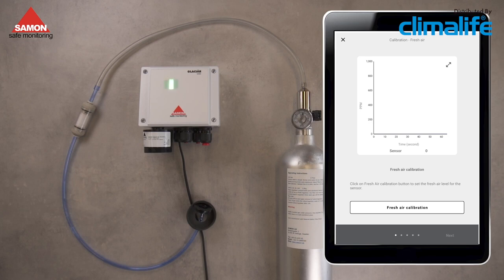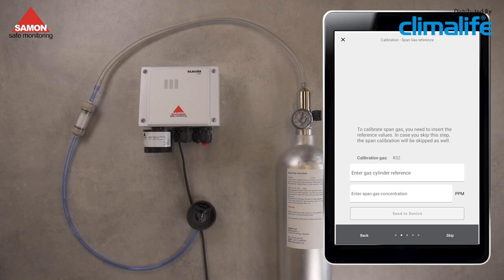Before connecting the calibration kit, make sure the sensor is ready and free of gas or other sources of pollution. If a clean environment can't be made, use natural fresh air for zero calibration. Click Fresh Air Calibration at the bottom, then select Next. To perform the calibration, the specific gas indicated as the calibration gas needs to be used. For Group 1, this is R32.